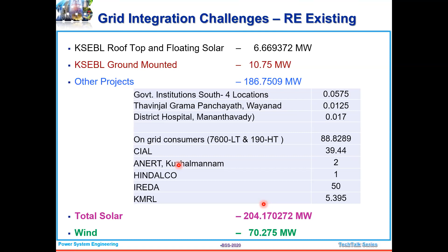We are planning to have an additional 1000 megawatt solar by the end of the 13th plan - about 500 megawatts through rooftop solar generation, a distributed injection through the distribution network, which may cause some problems in the future. Then 500 megawatts through ground mounted floating solar. The main issue here is power evacuation, because the floating solar will come up in reservoirs in forest areas where we don't have any network as of now - we have to plan for additional network in that area.